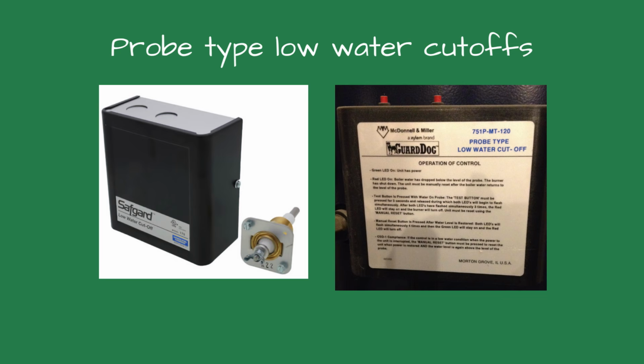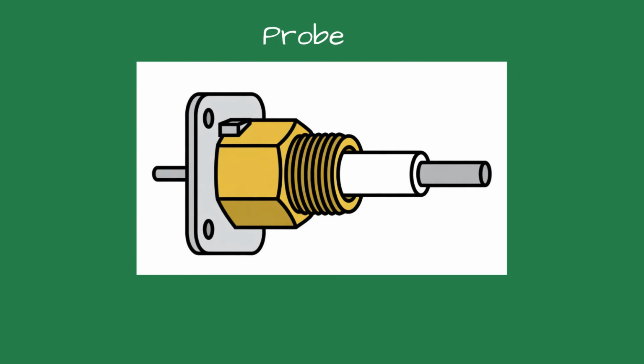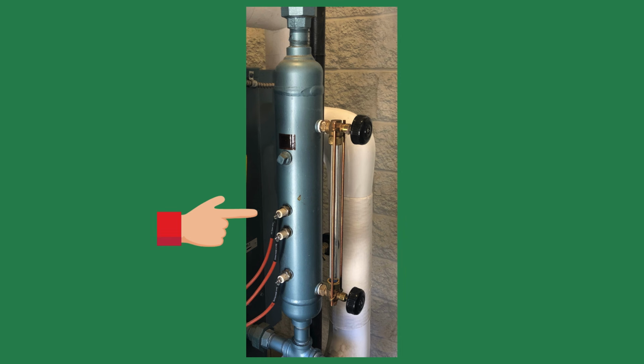Probe type low water cutoff is relatively new compared to the float type. The float type was invented about 100 years ago, while the probe type has been around for less than half that time. It's a simple design that uses conductivity of the water to verify the boiler or system has enough water. The probe is basically a metal finger that checks the system water level.